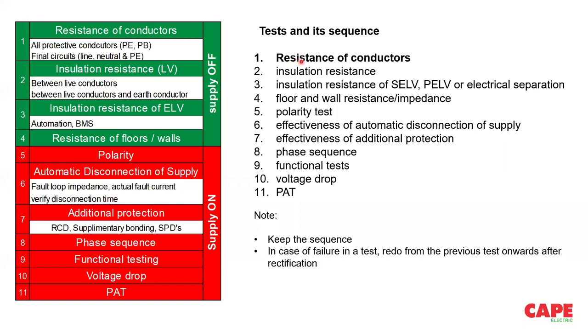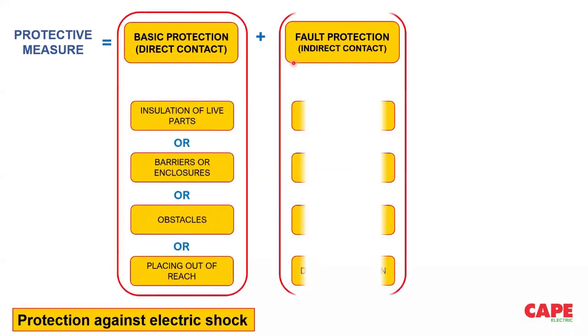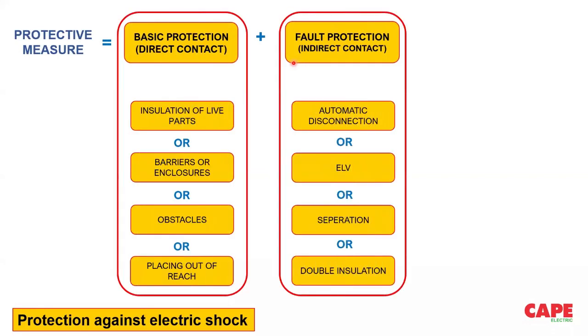So I will explain the first one, resistance of conductors. In the next 2 slides, I explain the first inspection point and the first testing point, so that you can ascertain the situation of electrical safety in your building. Now, protection against electric shock. There are several techniques. Basically, you need to have basic protection. You need to have fault protection. Basic protective measures are there, such as live part, barriers, obstacles, placing out of reach. Fault protection includes automatic disconnection, ELV, separation, double insulation. There are different techniques.